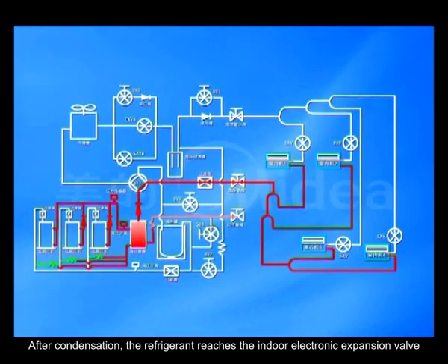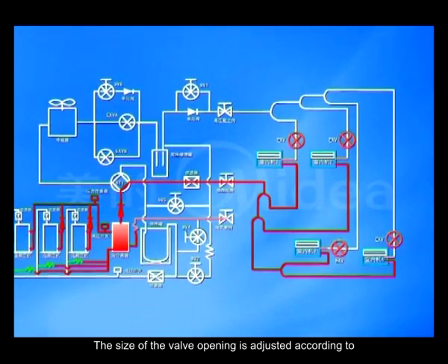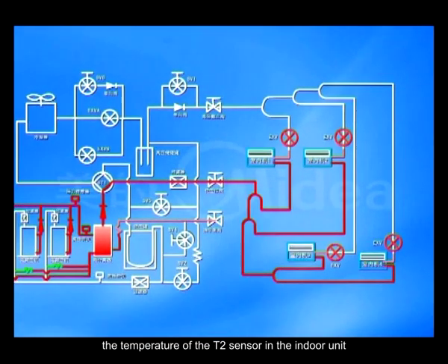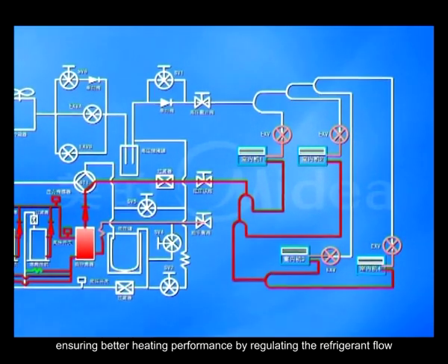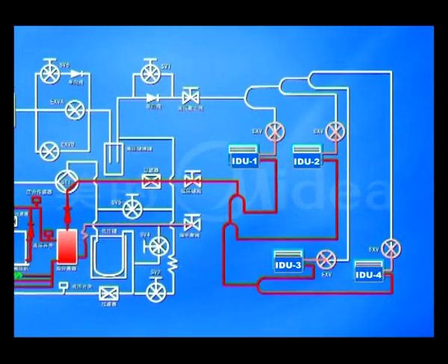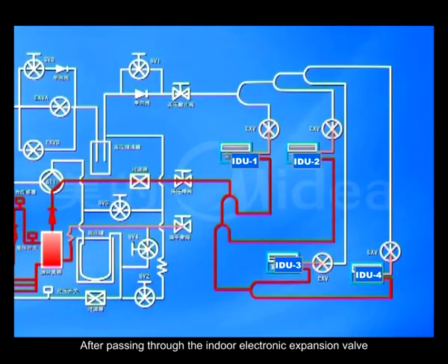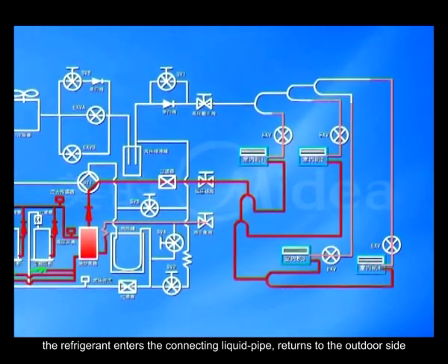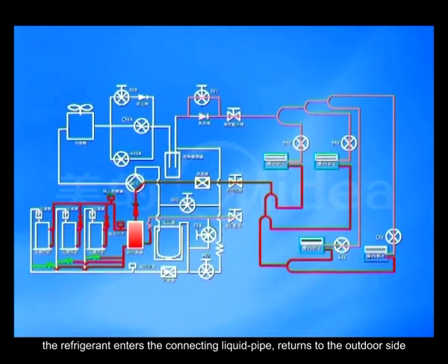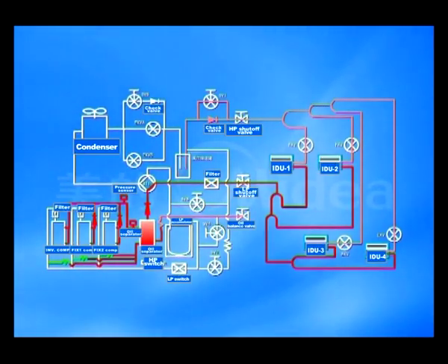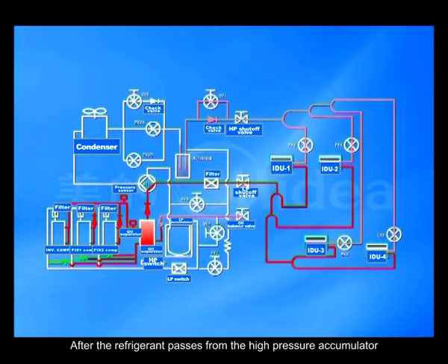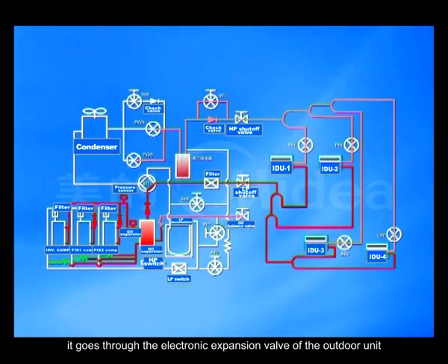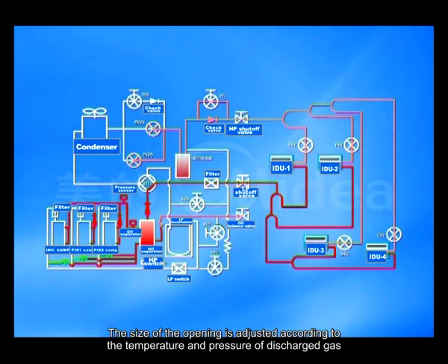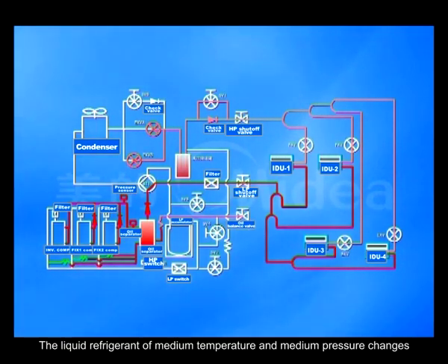After condensation, the refrigerant reaches the indoor electronic expansion valve. The size of the valve opening is adjusted according to the temperature of the T2 sensor in the indoor unit, ensuring better heating performance by regulating the refrigerant flow. After passing through the indoor electronic expansion valve, the refrigerant enters the connecting liquid pipe, returns to the outdoor side, and enters the high-pressure accumulator in the outdoor unit. After the refrigerant passes from the high-pressure accumulator, it goes through the electronic expansion valve of the outdoor unit. The size of the opening is adjusted according to the temperature and pressure of discharged gas. The liquid refrigerant of medium temperature and medium pressure changes into gas-liquid refrigerant with low temperature and low pressure by throttling.